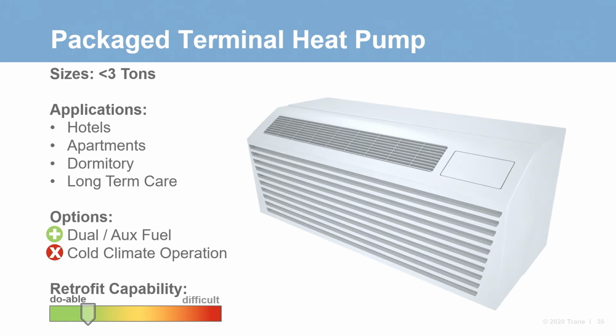If there is already an opening in the building that contains a PTAC, going with a packaged terminal heat pump with the same chassis is very doable. If the building you're looking to retrofit does not have air conditioning at all, cutting an opening in the side of the building to accommodate a packaged terminal heat pump might be a bit of a hurdle, but potentially a lot easier than other system options.